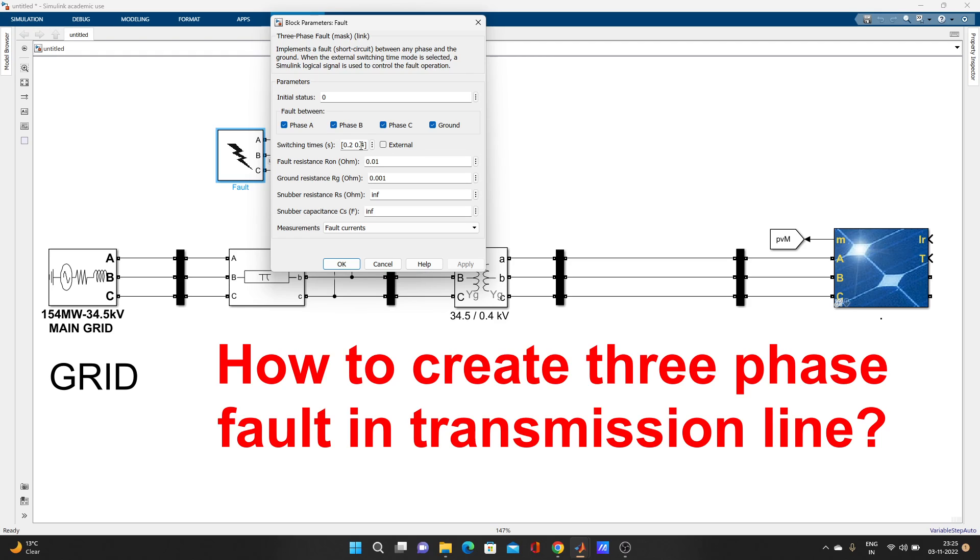And this switching time is given here 0.2 to 0.4. Suppose I am running my model for 0.5 second. So at 0.2 second, that fault will create in the model, and up to 0.4 it will be there. That fault condition, phase ABC to ground fault condition, will be there from 0.2 to 0.4.